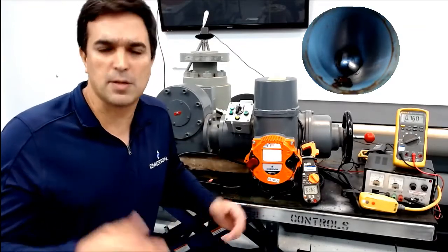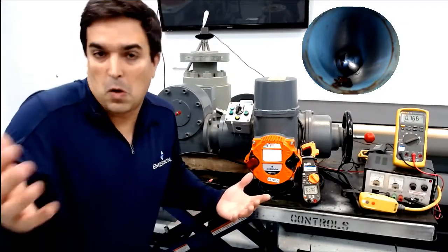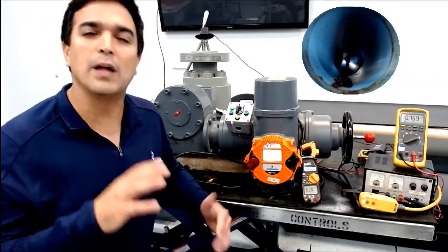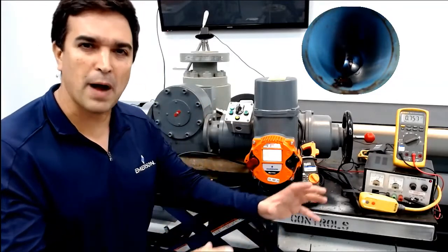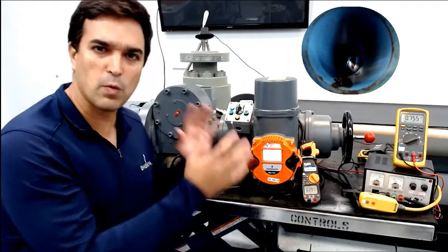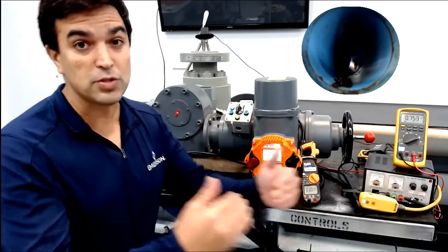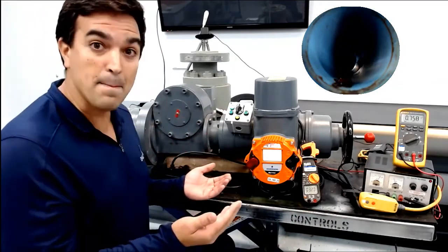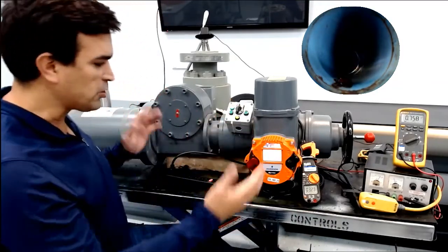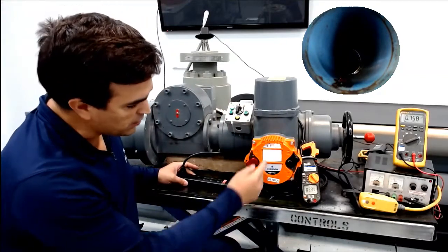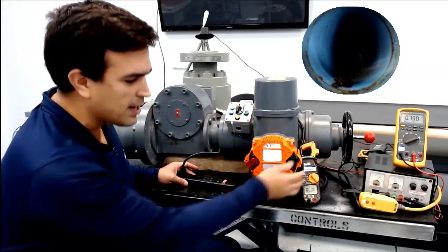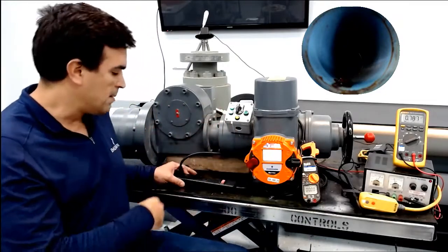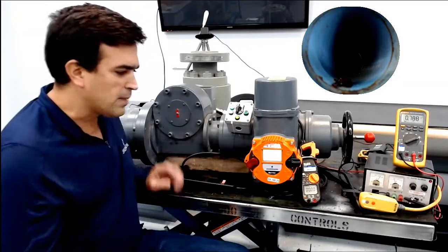What happens if you lose the main power? Maybe you want to close the valve because you lost the main power, but maybe not. Maybe you want to set your application, or your pipeline, your process, whatever you are controlling with this shutdown valve, maybe you want to close it after something else happened. So let me show you what can happen when you lose main power supply in this demonstration. So there you go. The valve is 100% open. You can also see on the video how the valve opens and closes. But there you go, the valve is open, you lost main power.